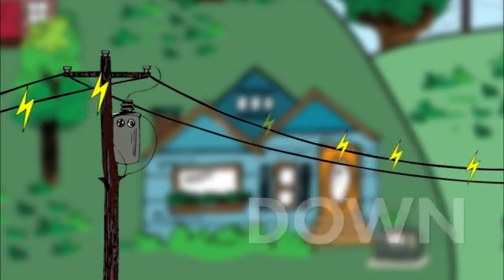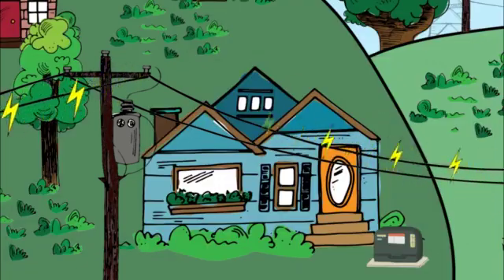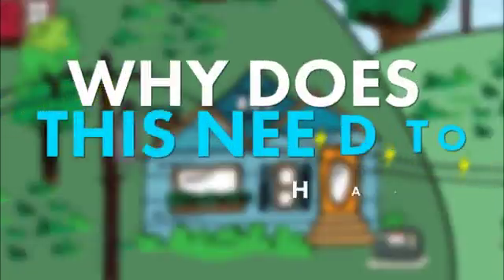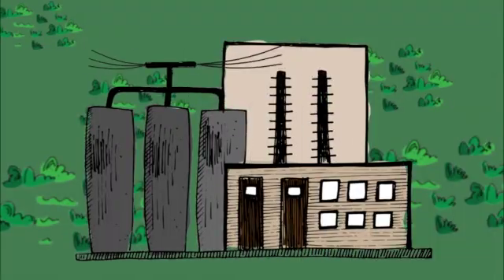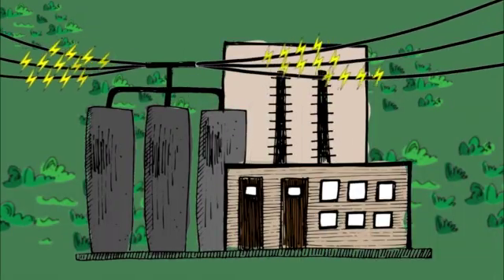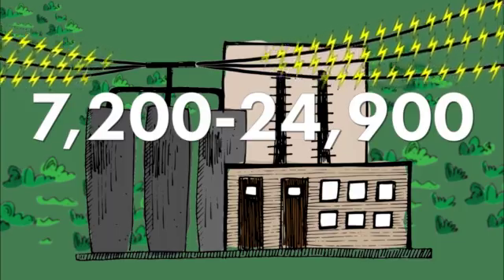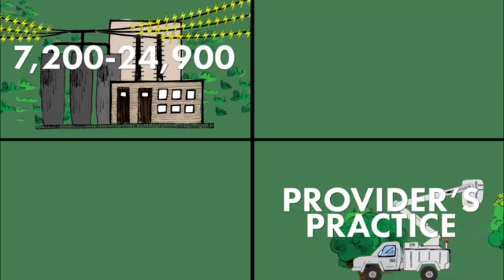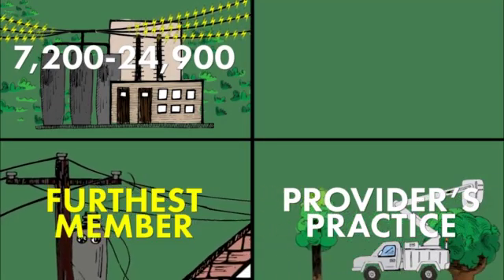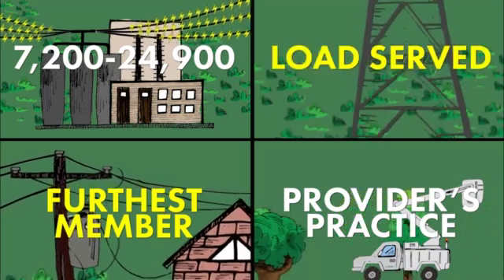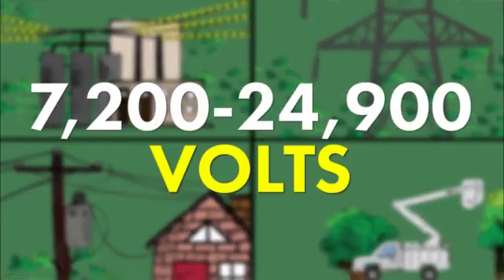Transformers are used to step electric voltage up or down before it makes its way to its final destination. Why does this need to happen? Original power distribution voltage can range from 7,200 to 24,900 volts, depending on your electric utility provider's practice, the distance to the furthest member, and the amount of load served. That's much too high a voltage for safe home or business use.